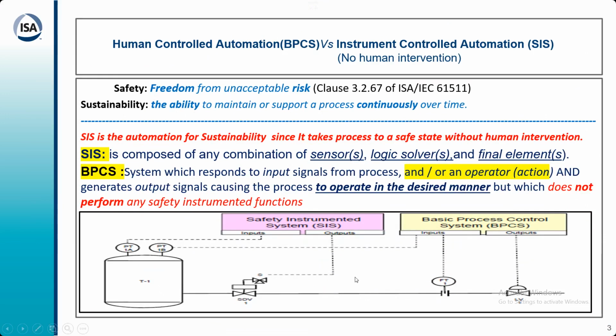Now BPCS, if you look at this, is a system where a transmitter is there and a control valve is there, which is a regulating valve. This is not an on-off valve. It will regulate. A pressure sensor is connected here, and you have to control the pressure depending upon the requirement of the pressure control. Here is a valve, and the flow is being controlled by BPCS. As long as BPCS is functioning all right, the process is safe. You are in the safe state of the process. You have given a set point, and BPCS is controlling this control valve and maintaining the process parameter around the set point. But what if this BPCS fails?